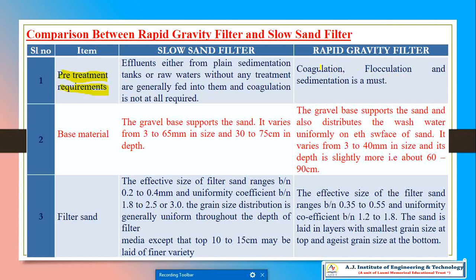Coagulation, flocculation, and sedimentation are required in the rapid sand filter because the rate of filtration is high. Therefore, the water must be coagulated and flocculation has to be done in the sedimentation tank, otherwise fine particles cannot be removed in the rapid sand filter. But for the slow sand filter, just plain sedimentation is enough — without any coagulation, water can be directly fed into a slow sand filter.